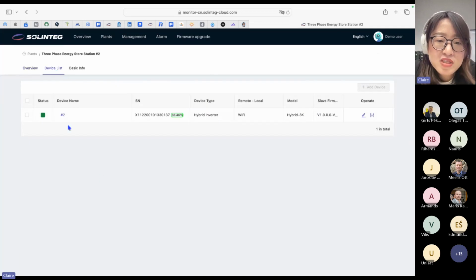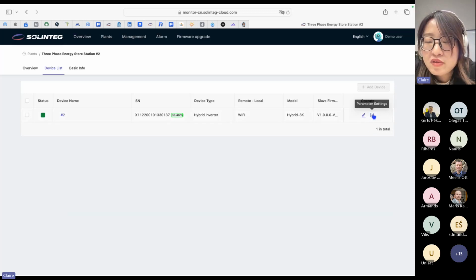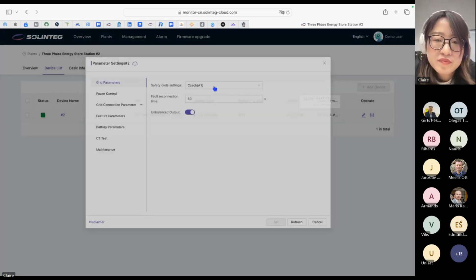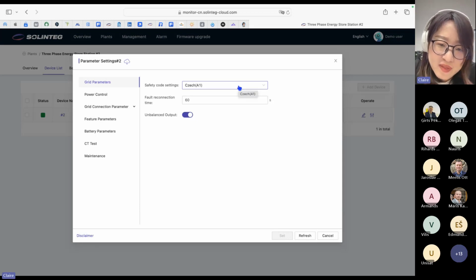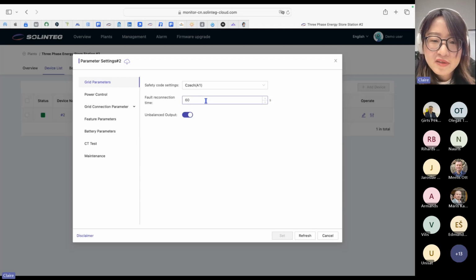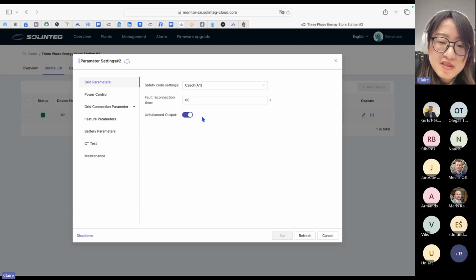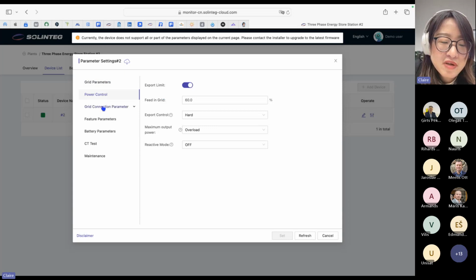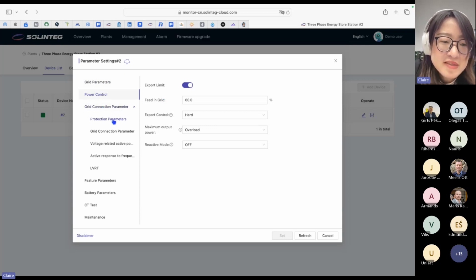And this is the device list information, so we can see the inverter serial number and this inverter's battery level. This inverter uses a Wi-Fi connection. We can also see the model of the inverter and the firmware version, and we can do the parameter setting of the inverter. So we can select the country code and set the fault reconnection time and the unbalanced output. This function is not open by default, so if you want to use unbalanced output, you need to manually open this. Yeah, there are some other parameters you can manage or amend here.